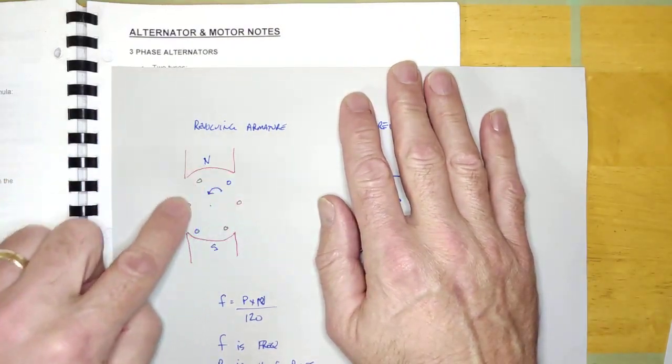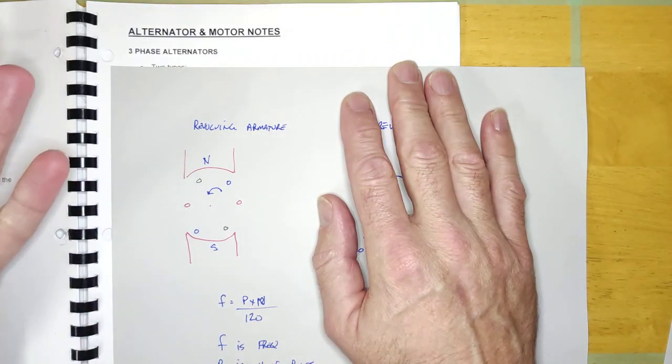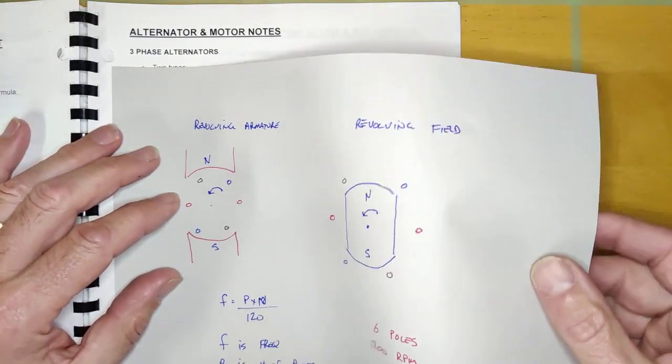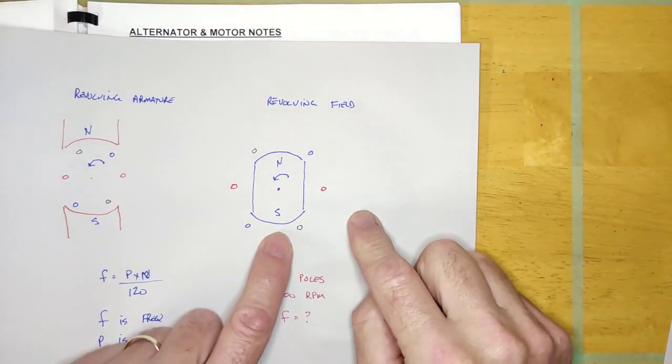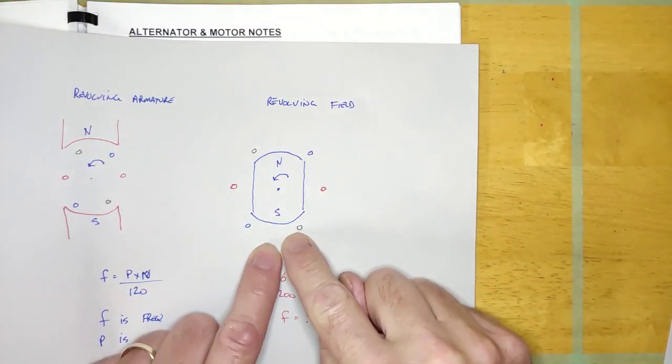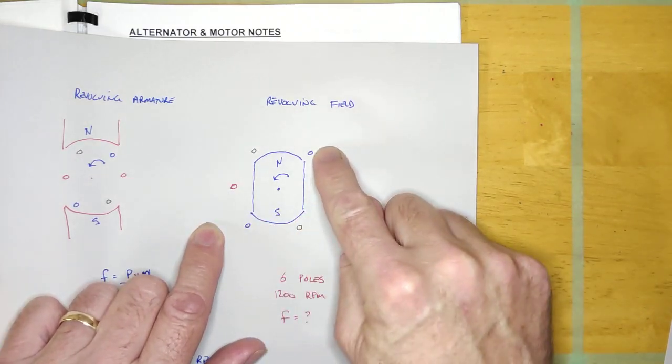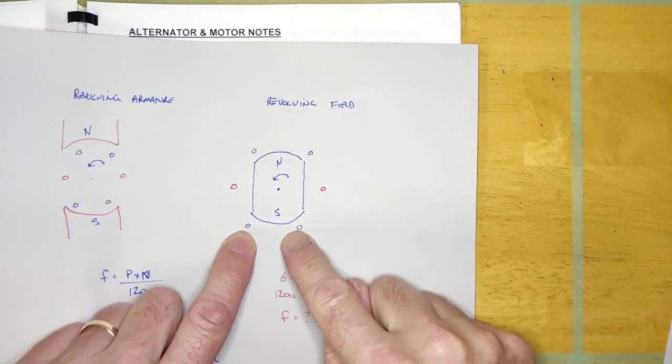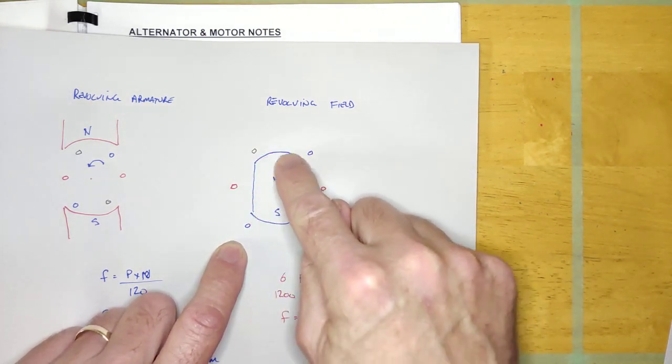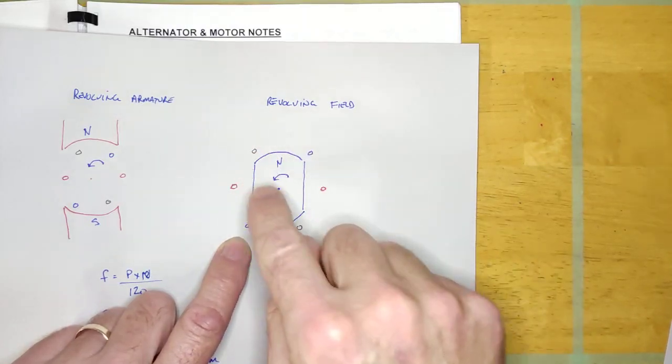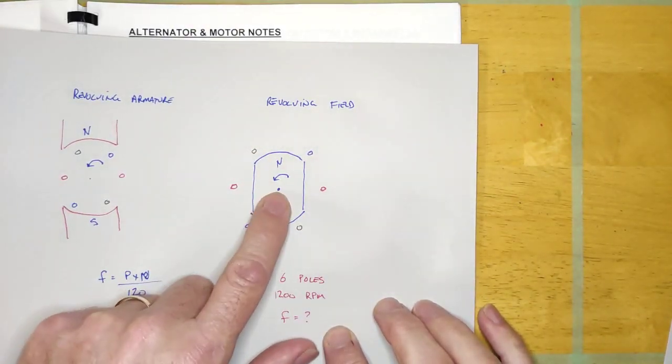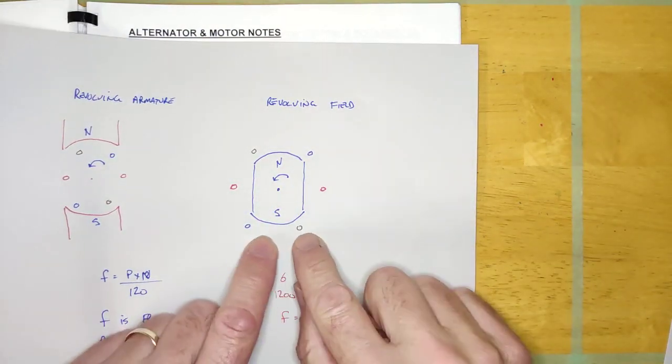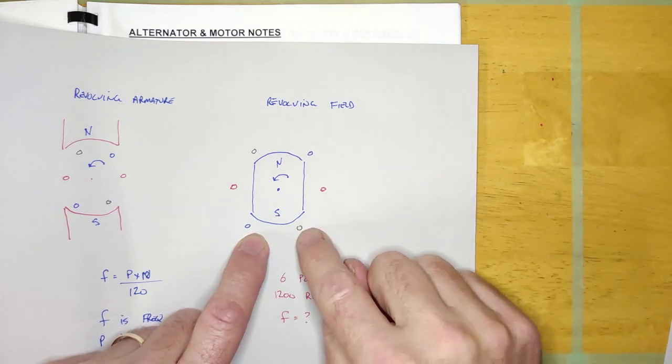That is what's known as the revolving armature type generator. It's used all the time for small machines, but on a larger alternator or generator, what we're probably going to find in real life is the actual conductors are fixed around the outside and we rotate the magnetic field instead. Here's my three phase windings that will have voltage induced into them, and we just put a magnet on the inside and whip that around.